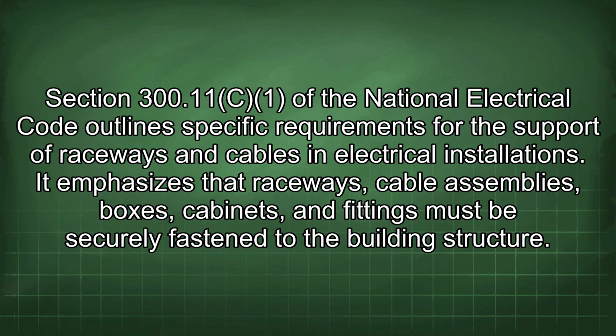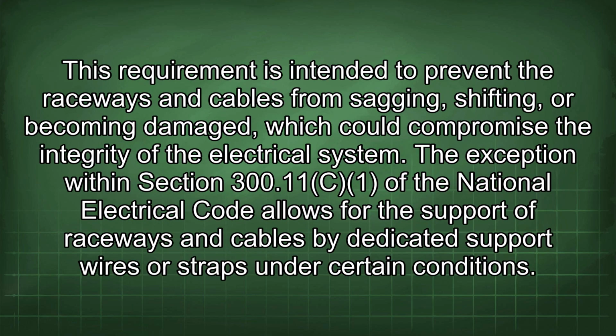Section 300.11(A) of the National Electrical Code outlines specific requirements for the support of raceways and cables in electrical installations. It emphasizes that raceways, cable assemblies, boxes, cabinets, and fittings must be securely fastened to the building structure. This requirement is intended to prevent the raceways and cables from sagging, shifting, or becoming damaged, which could compromise the integrity of the electrical system.